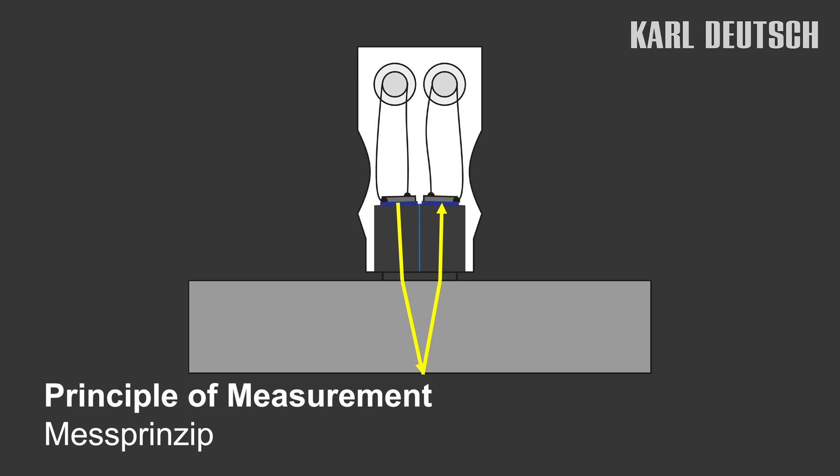The ultrasonic pulse is sent into the material by the probe. It is reflected at the back of the wall and returns to the probe as an echo. The ECHOMETER measures the time until the sound returns to the surface. The wall thickness can be determined from the time measurement and the known sound velocity of the material.